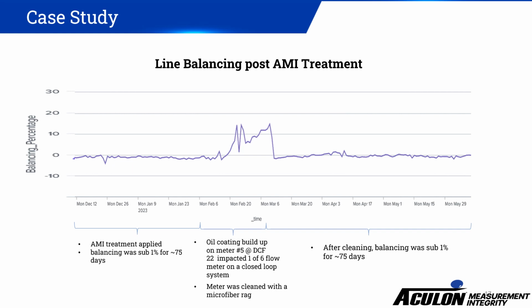We found that oil coating buildup had started on meter number 5 at DCF 22, impacting only one of the 6 meters on the closed loop system, not the outlet meter. This meter was then pulled, cleaned with a microfiber cloth, and rolled back into service. After the cleaning, the balancing stayed sub 1% for another 75 plus days. We then placed our control group meters back into service to see if water quality had changed or if something else in the system was affecting it.